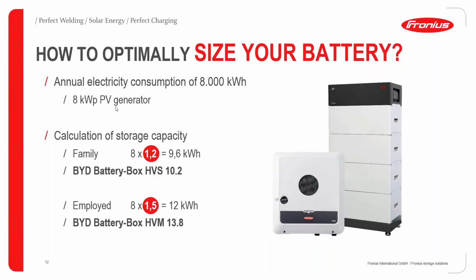You just have to look at the annual electricity consumption, which is around 8,000 kilowatt hours, and take the kilowatt peak of the PV generator installed on the customer's roof. Then you calculate using the factor 1.2 for the family profile and 1.5 for the employed person profile, and you receive the battery storage capacity in kilowatt hours, roughly. That's the basic rule of thumb.